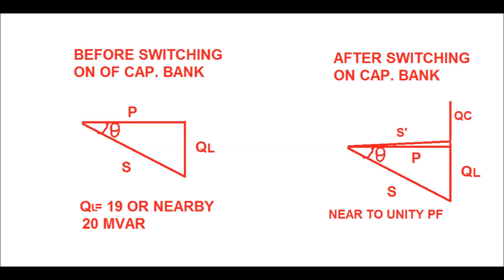If Q_L is equal to or close to 20 MVAR, then after switching on the capacitor bank it will completely nullify the lagging reactive part Q_L that was earlier supplied by the system. Therefore the power factor angle comes close to zero and the power factor comes close to unity. That is how the power factor is improved by switching on the capacitor bank.